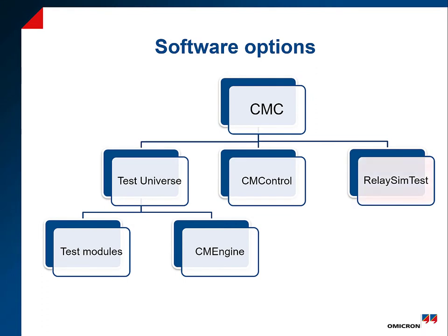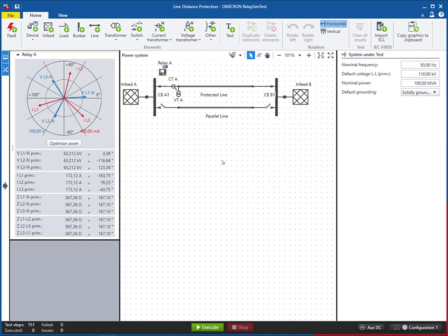RelaySimTest is a good complement to relay testing with Test Universe. It represents system or simulation-based testing as an addition to the parameter-based approach in Test Universe. It is another software option for CMC test sets which simplifies complex protection scheme testing, validating the correct operation of a protection system by simulating realistic power system events.